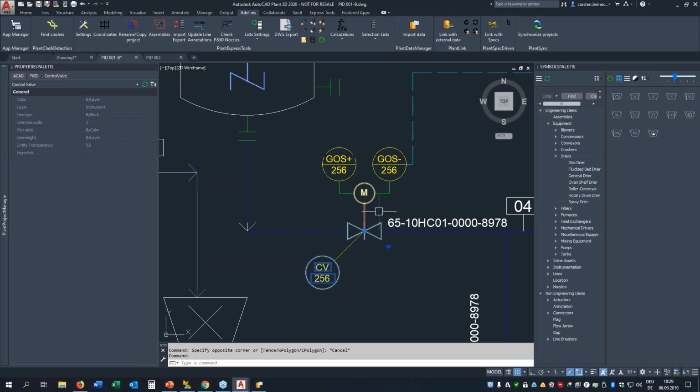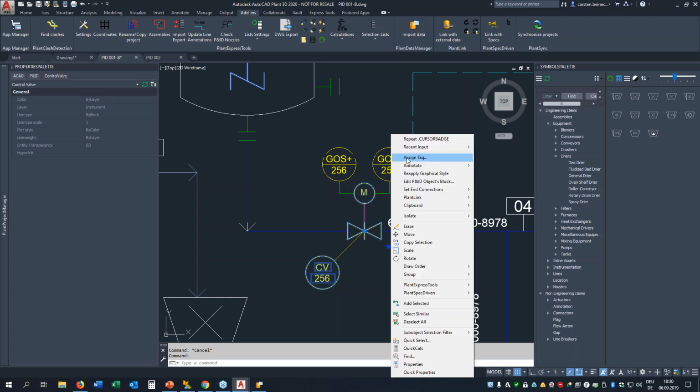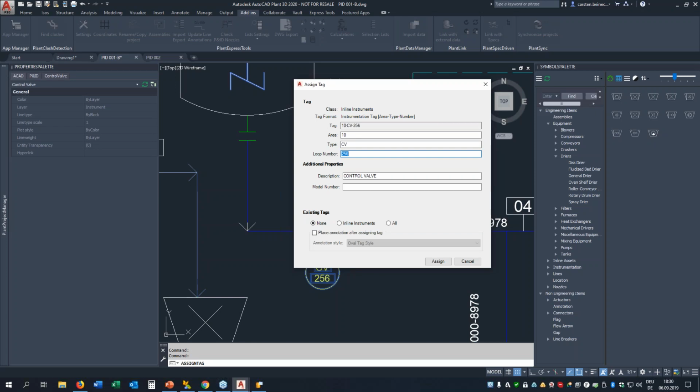And in the database, in the P&ID database, I get all that information. I know which actuator is connected to what control valve. I know that this symbol is connected to that control valve by this line, and I know because of that signal line what is at the end and at the start of that line. So I can let data flow between symbols. And yeah, I will just show this with the loop number here.